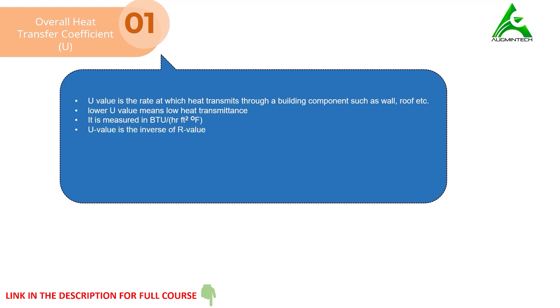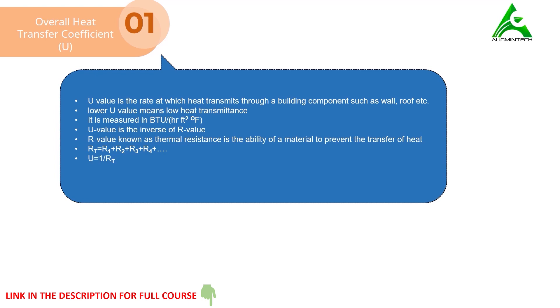U-Value is the inverse of R-Value. R-Value, most commonly known as thermal resistance, is the ability of a material to prevent the transfer of heat. The higher value of R means the building components won't allow heat to travel into the system easily. To find the total R-Value of a building component, the individual resistance of each component is calculated and added accordingly, then U-Value is found by simply taking the inverse of the total R-Value.